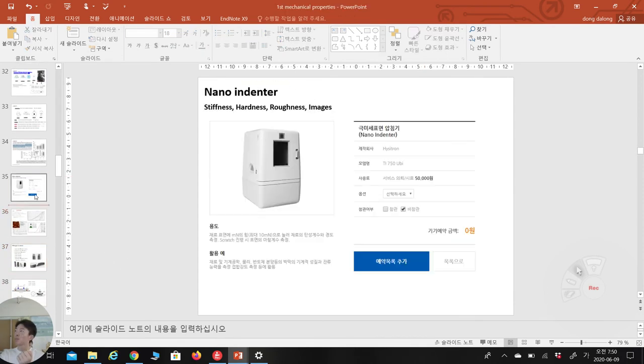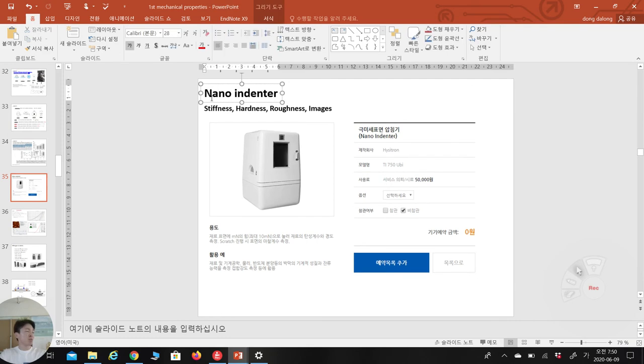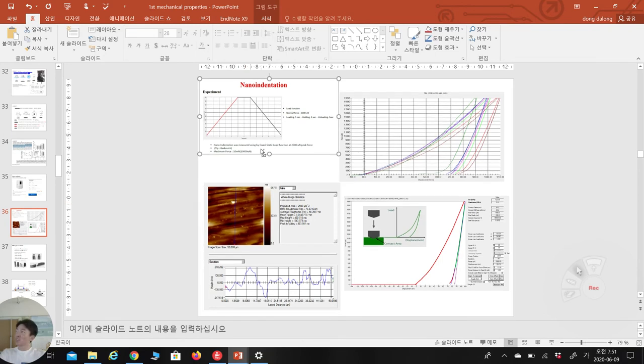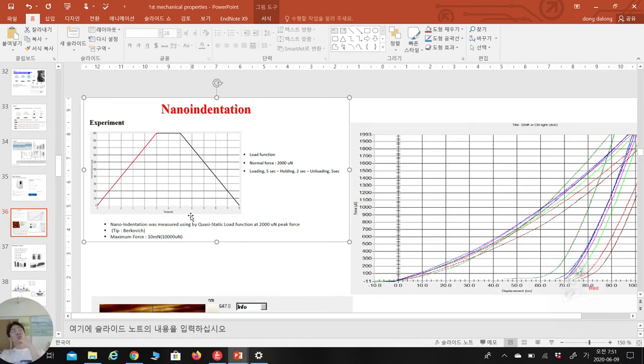How about the size? Do you know the size? Size of what? For checking with the nano indenter? Any size is okay. This is nano. Anyhow, I will show you this example. Maybe this is our titanium disc. The specimen should be flat. That is better, because when it is a little bit angled, it's not easy to detect, but anyhow, they can measure. A flat surface is okay, and the size doesn't matter. They can detect any size. But it should stand on the surface, not floating.